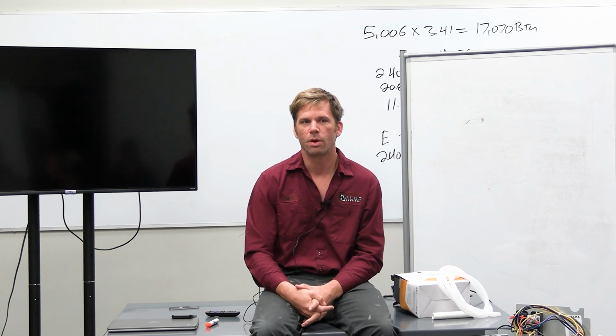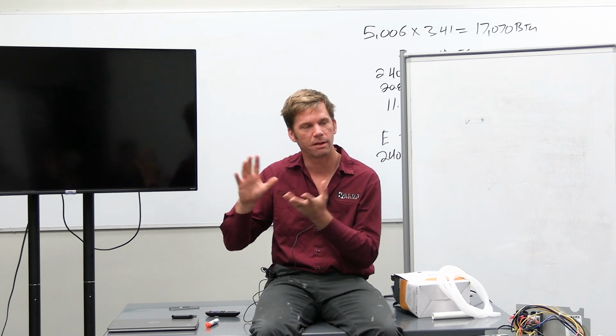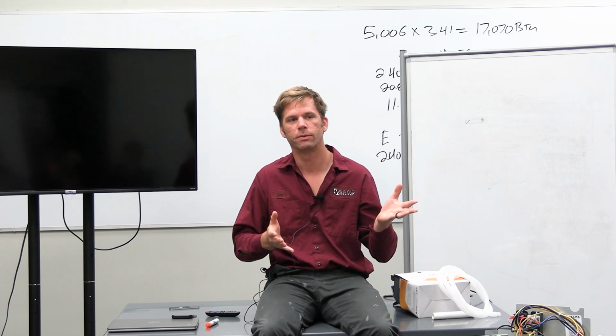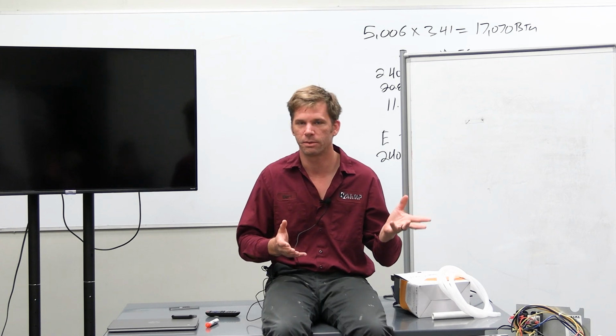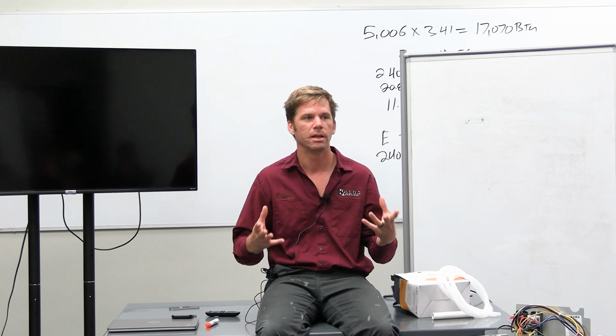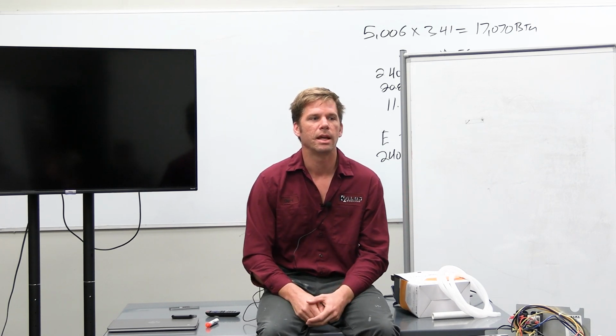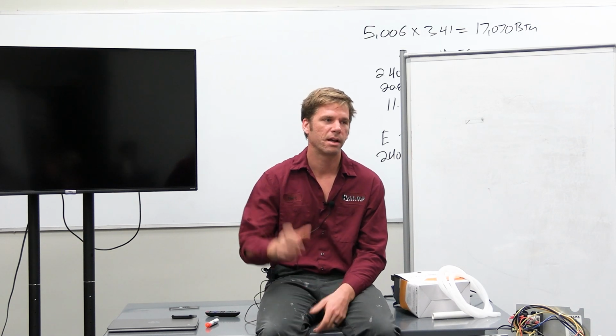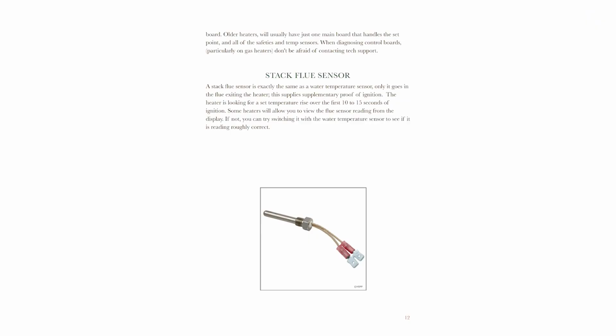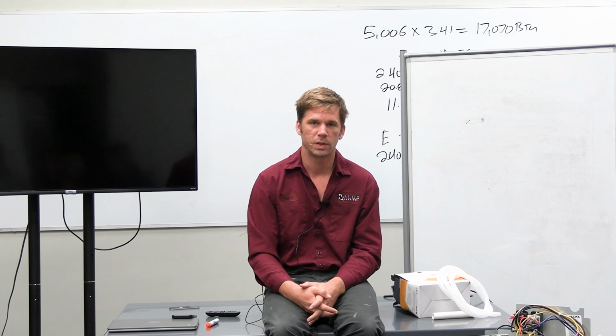And so what will happen is it might have been enough airflow for the heater to come on, but it's not enough to get rid of the amount of heat that we're dealing with. The heater starts getting hot, and you will have a sensor called a stack flue sensor that sits straight into that exhaust pipe, and it chops out, bringing the heater off once it gets too hot. In that situation, you need to open up your blower compartment, you need to check your flue pipe, and make sure you have good airflow. Sometimes those sensors just go bad.